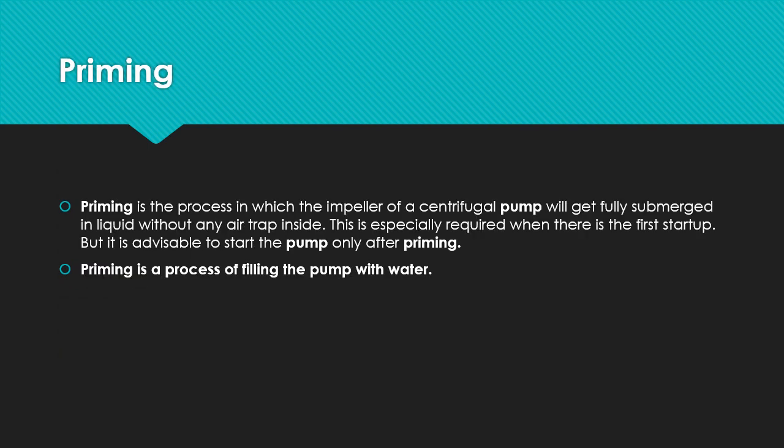Priming is one of the most important phenomena in pumps. In centrifugal pumps, priming is required, whereas reciprocating pumps do not require priming. Priming is the process of filling the pump with water so that there are no air bubbles or gaps present. It is the process in which the impeller of a centrifugal pump gets fully submerged in liquid without any air trap inside. This is especially required at first startup, but it is advisable to always start the pump only after priming.